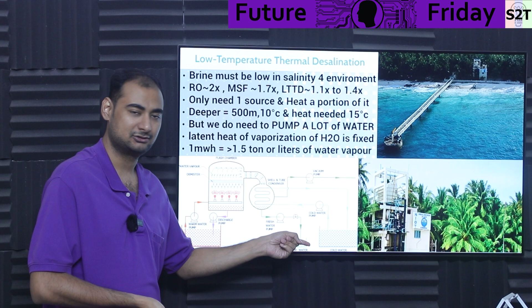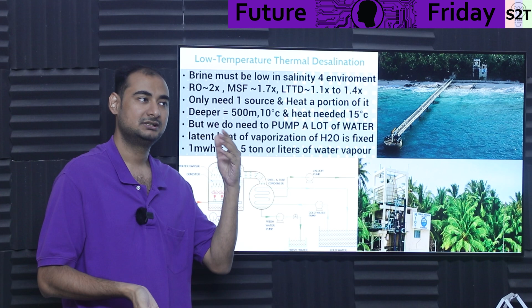You might think that makes a sloppy heat sink, but no. It's very cold, so if you pull water from that depth at 10 degrees Celsius, your heat naturally wants to go there. You get a magnificent COP, and since water is denser than air, it takes a lot of energy just to raise its temperature from 10 to 15 degrees.